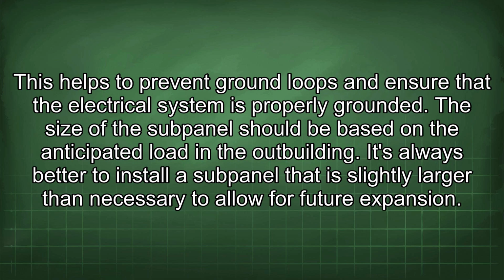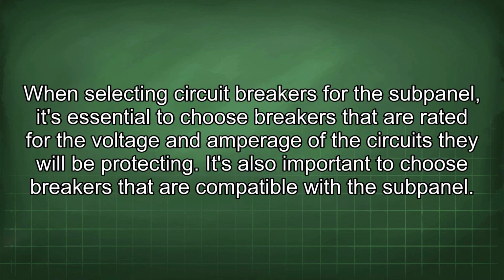The size of the subpanel should be based on the anticipated load in the outbuilding. It's always better to install a subpanel that is slightly larger than necessary to allow for future expansion. When selecting circuit breakers for the subpanel, it's essential to choose breakers that are rated for the voltage and amperage of the circuits they will be protecting. It's also important to choose breakers that are compatible with the subpanel.